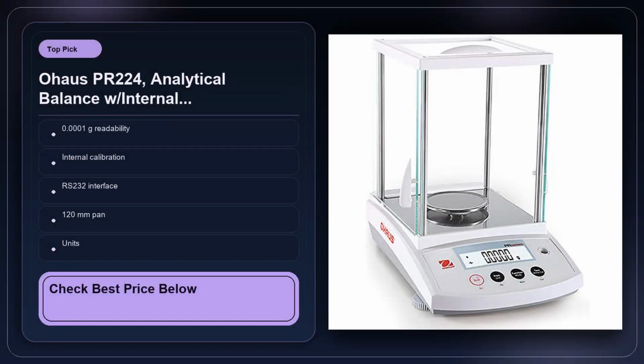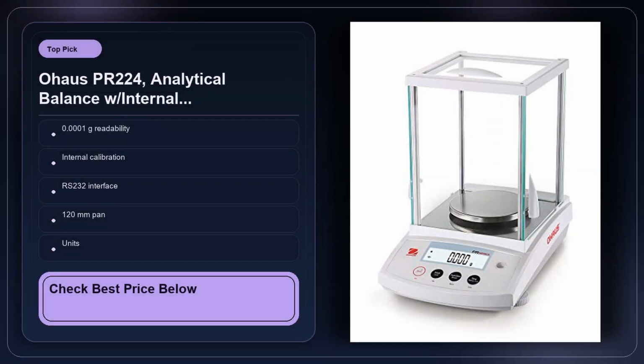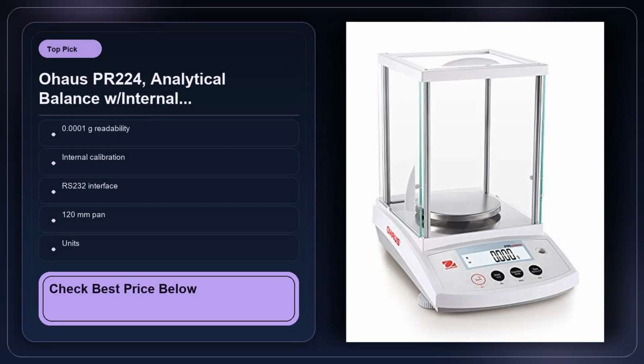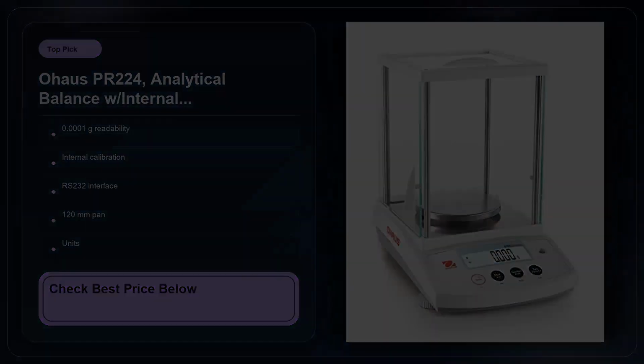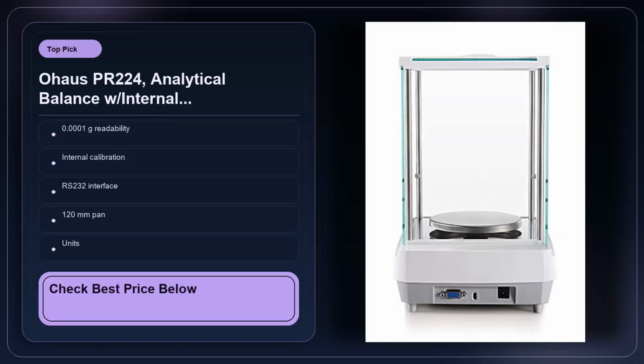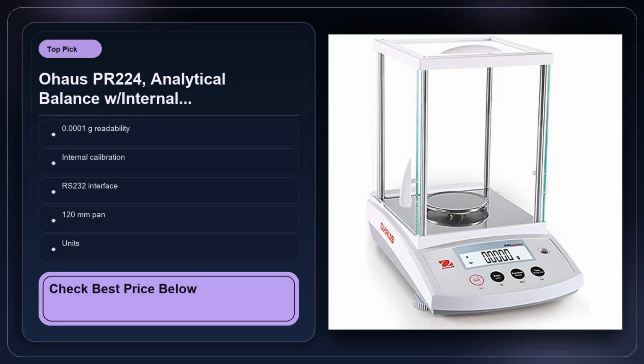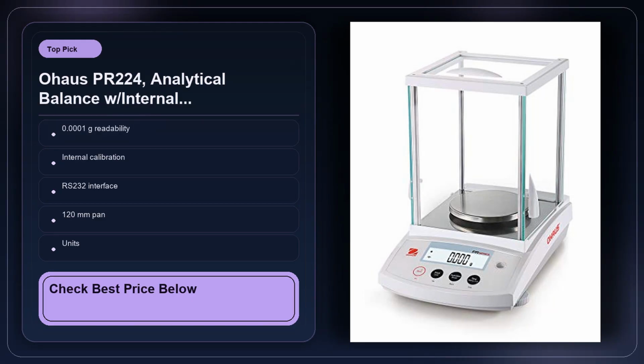Now, let's talk about the hidden trade-offs. The 220-gram capacity is generous for an analytical balance, but you have to remember the readability limit of 0.0001 g. If you try to push the balance near its maximum capacity, the resolution effectively drops, and you might start seeing more noise in the readout. In practice, I've found that staying under about 150 grams gives you the cleanest data. That's fine for most analytical tasks, but if you routinely need to weigh larger quantities with high precision, say, bulk solid dosing for formulation work, you'll start to feel the constraints.